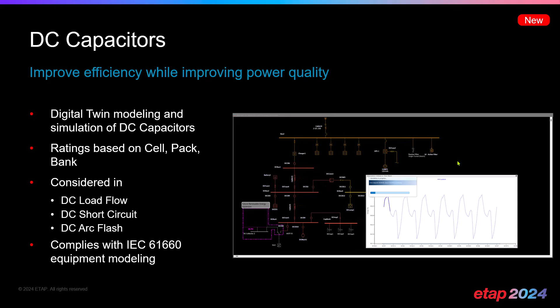And then we've also enhanced, of course, the algorithm for faster convergence for special systems as well as large systems by essentially utilizing multiple core capability or multi-CPU capability. We've also added, of course, our DC capacitor as a new element, which is used for simulations in DC load flow, DC short circuit, as well as DC arc flash. And it also complies with IEC 61660 for its equipment modeling, as well as its rating, which you can specify based on cells, packs, as well as banks of capacitance. So this opens up, again, new doors in terms of evaluation of renewable energy systems, DC railway systems, as well as high pulse power applications.